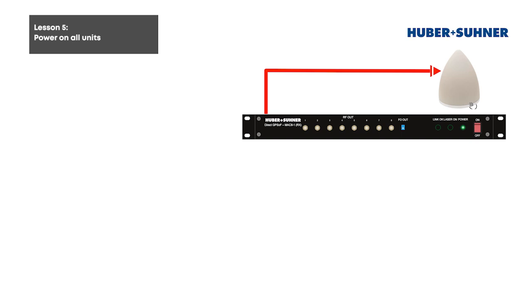The automatic test and reboot function assures an automatic restart of the direct GPS-over-Fiber system as soon as power is back on after a blackout at the facility in which it was installed. Check if the fuse is functional, and if not, replace with a 2.5 amp slow-blow 250-volt fuse. Once the safety system has confirmed that all connections are in place, the Link On and Laser On LEDs will turn on. These two LEDs confirm that the link is functional.